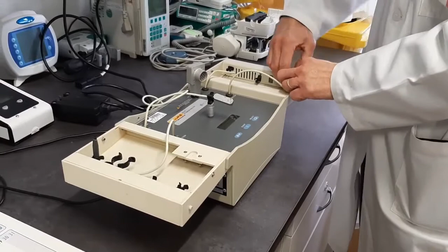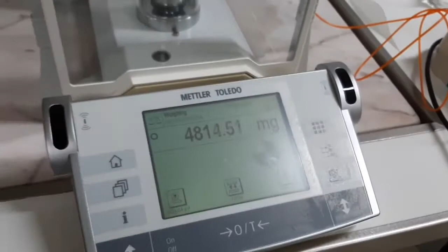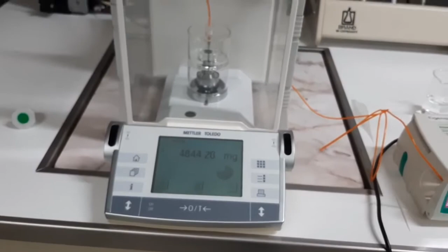The verification of the conformity of several sensors incorporated in infant incubators are also examples, namely for air temperature, relative humidity, and carbon dioxide sensors. The metrological verification of these multi-parametric monitors is carried out using simulators. The metrological traceability of medical devices is an essential requirement to assure the accuracy of its measurements.